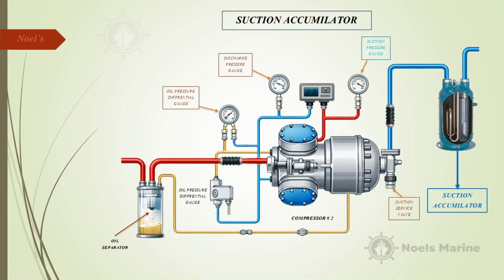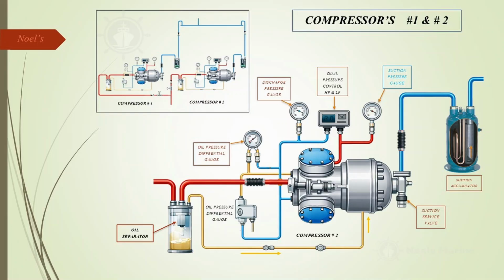So it's basically an insurance policy for the heart of the system, which is step 3, the compressor. The heart is a great way to describe it. This is where the heavy lifting happens. Ships usually have 2 of these, by the way, one running and one on standby for safety. Though if the load is really heavy, they can both run. So what is the compressor actually doing to this low-pressure gas? It takes that low-pressure vapor and just squeezes it. It crushes it into a tiny volume. And physics dictates that when you do that, the pressure skyrockets and the temperature skyrockets. So we get high-pressure, very high-temperature gas.